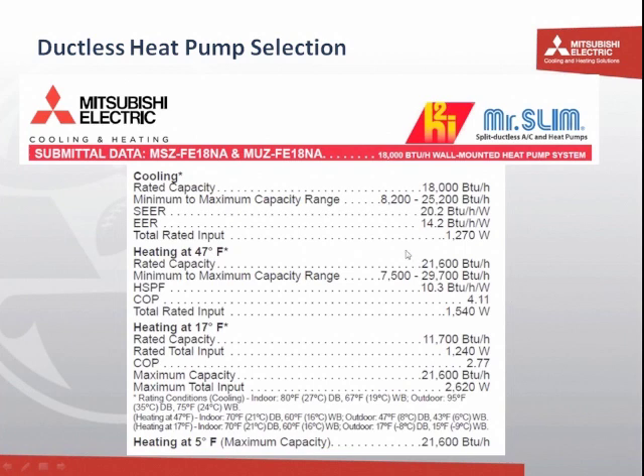You can see that it has a range of 8,200 to 25,000 BTUs. This is taking advantage of that inverter where we can dial it back all the way down to less than half of its capacity, or dial it up to in excess of its nominal capacity for that quick cooling or quick heating burst that you might need if a space has been unoccupied and has now been activated. You can see the 20.2 SEER, so extremely high efficiency. Total rated input of 1,270 watts. That happens to occur at its nominal rated output. Those give you the cooling data that you need. So if your passive heat calculation or passive cooling calculation tells you that you've got a need for 16,000 BTUs total, you can see that that's well within the range of this unit and would be a good fit.